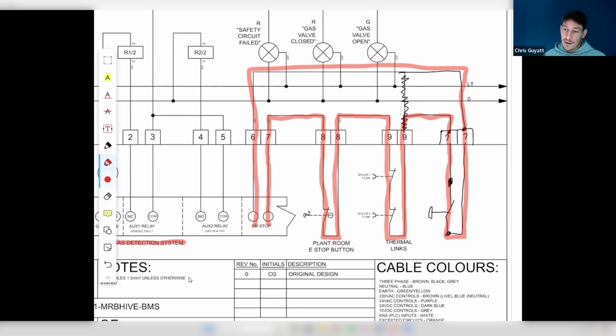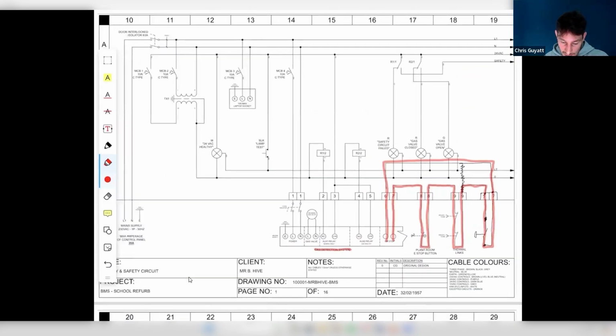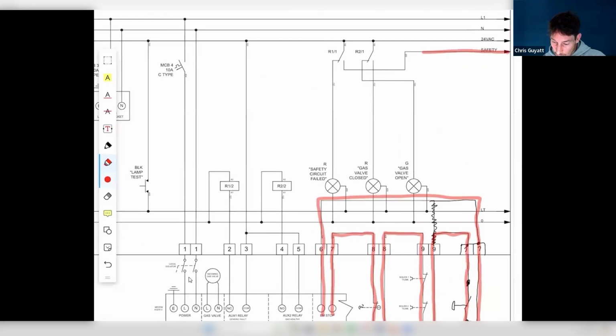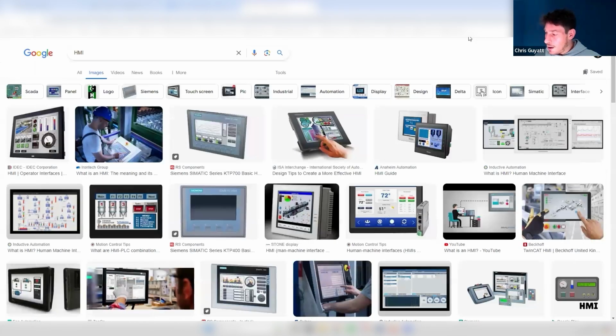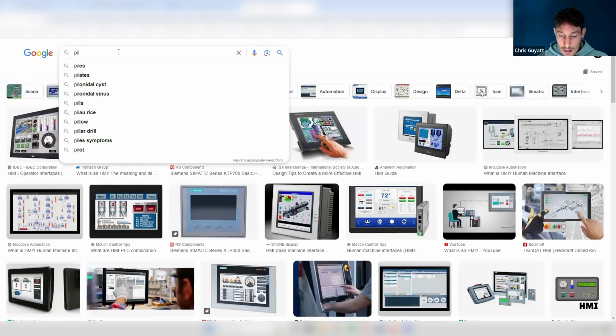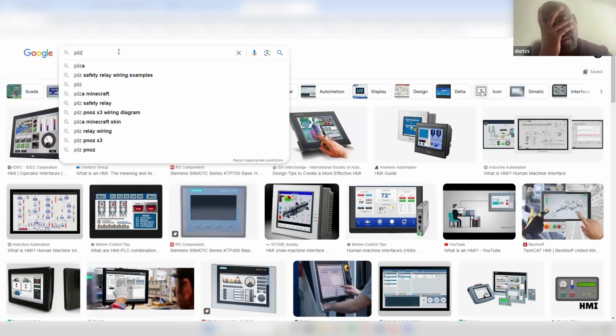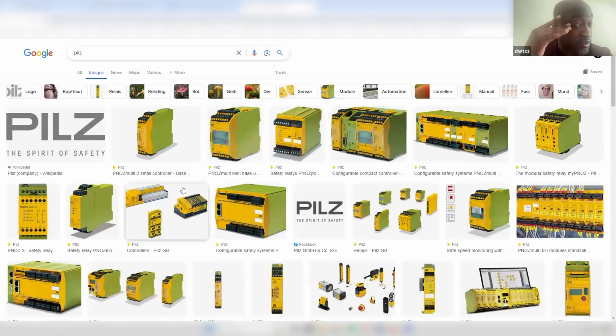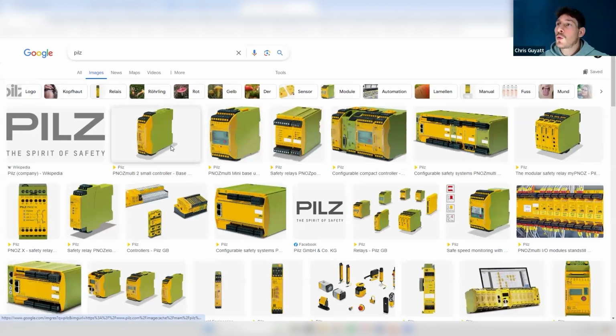Yeah, exactly. And so in a BMS, even though I refer to a safety circuit, it's important not to confuse that with a safety relay. And just so you guys are aware, let me show you what a safety relay looks like. Yeah, they usually come under the machinery directive, hence that's where you'd get the standard from. Yeah. And it's all determined through a risk assessment, ultimately, if you need to use a safety relay.